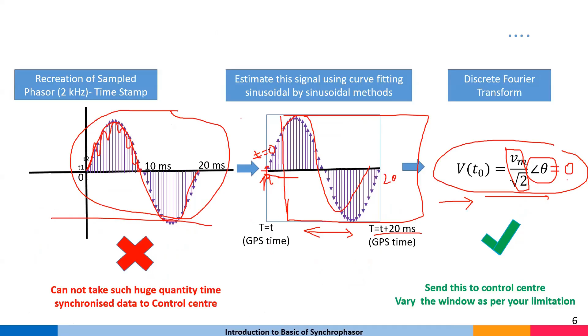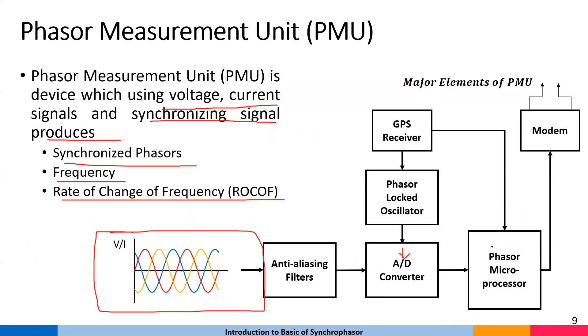This is the A to D converter. This particular time window is provided by the phasor processor, and t equal to 0 is whatever time the window has to start, provided by the oscillator, meaning the GPS receiver from which the phase lock oscillator is derived. The phase lock oscillator locks with the common GPS time frame and provides a signal to the analog to digital converter for generating a synchrophasor. This phasor microprocessor processes the data and sends it to the communication system, and from there it goes to the control center.